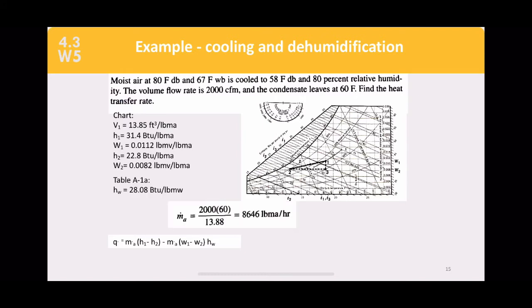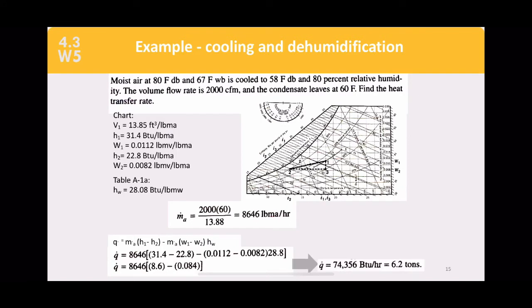Example for cooling and dehumidification: Moist air at 80°F dry bulb and 67°F wet bulb (State 1) is cooled to 58°F dry bulb and 80% relative humidity (State 2). Volumetric flow rate is 2000 CFM and the condensate leaving the coil is at 60°F. Find the heat transfer rate. You are given two points for State 1 to locate data on the psychrometric chart.